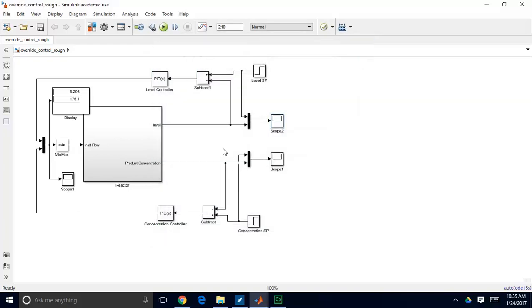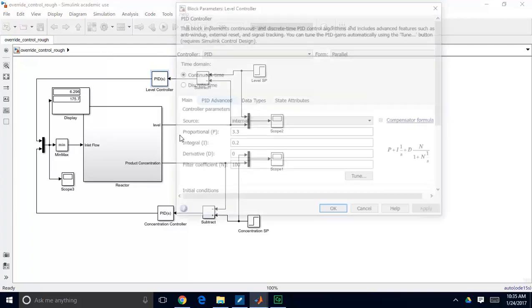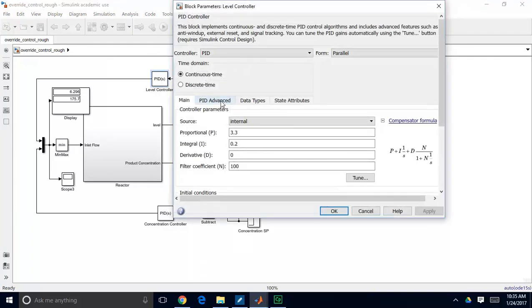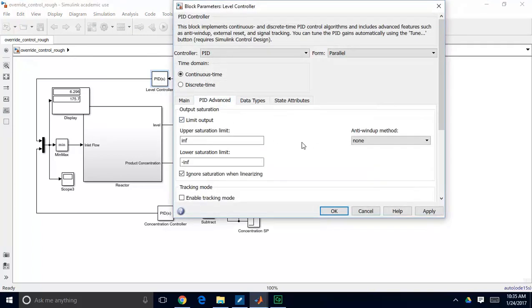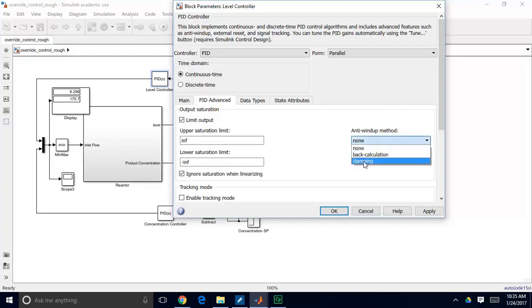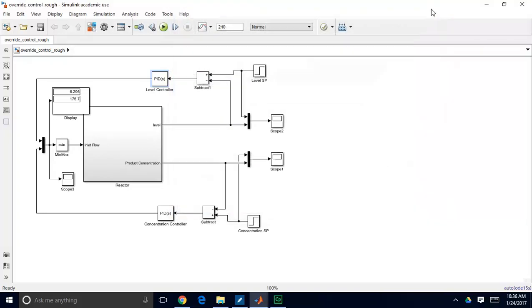So the way that we can handle this is similar to the way we handled control valve saturation. Remember in a previous demonstration that when our control valve reached 100%, that flow controller could no longer do anything, it could no longer reach its setpoint, so we introduced in our controller, we went to this option, and we limited our output, and then we chose an anti-windup method of clamping. So that anti-windup method basically stopped the integral part of the controller from integrating, so that we wouldn't get those large errors building up.